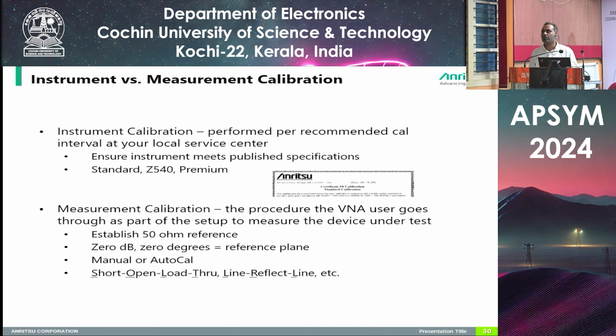This is done for the VNA, as I told previously, to remove the error or to establish a 50 ohm reference at the output of the port, or 0 dB or 0 degree at the end of the port. Okay, so this can be done using two methods. We can do it using a manual calibration kit, or using an auto calibration kit. In the manual calibration kit, as we discussed previously in the starting slides, we will be using the open, short and load. Using these three standards, we will be doing the calibration. Okay, so that is done in the mechanical calibration.